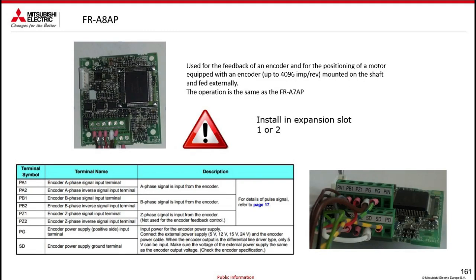Obviously, we also define a maximum resolution, which is 4096, readable and processable by this option that we can see here. The name is FR-A8AP. Below we can see our inputs, and I will bring my external power supply of 5 volts if it is a TTL, rather than 24 volts if it were an open collector, and SD is my reference common.